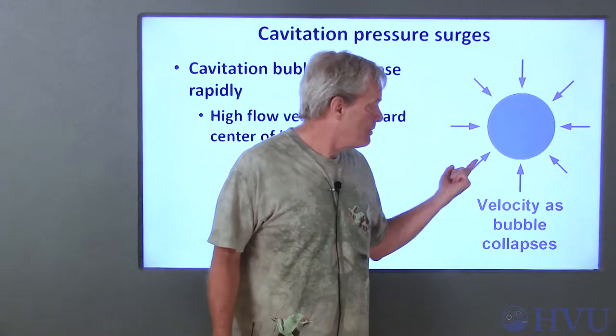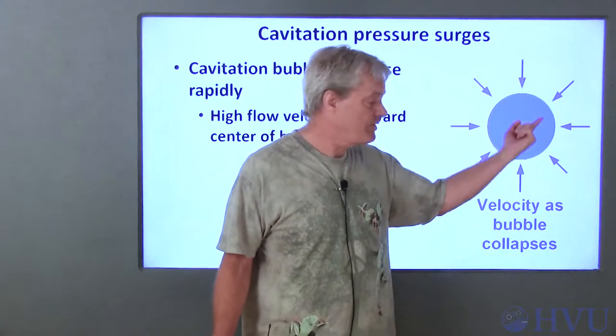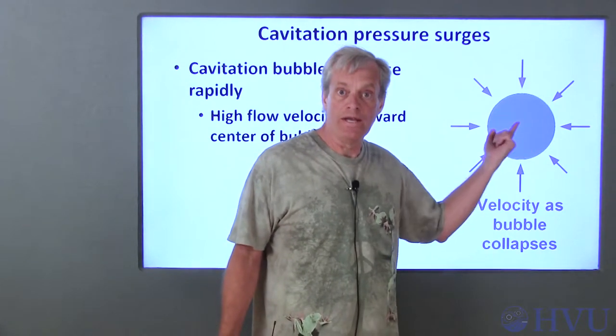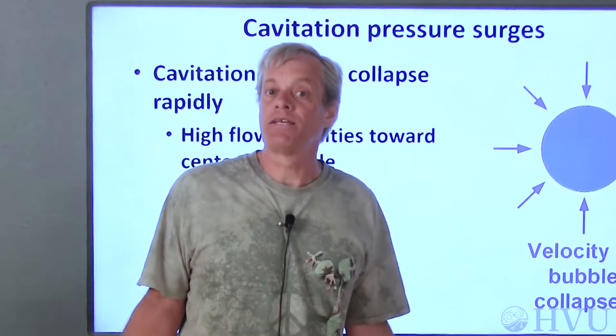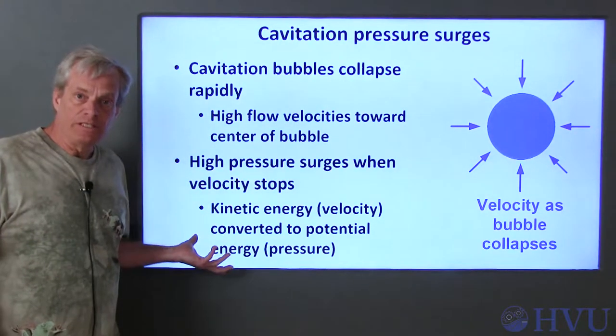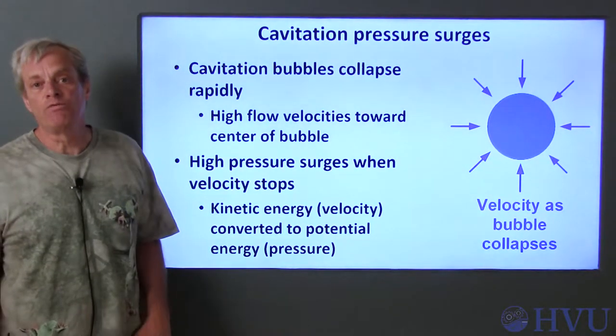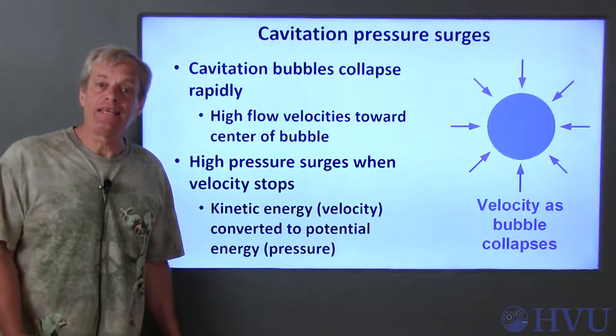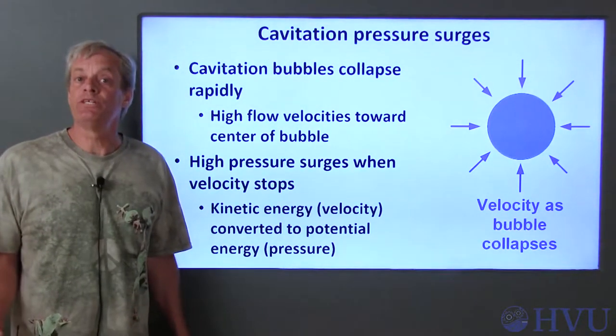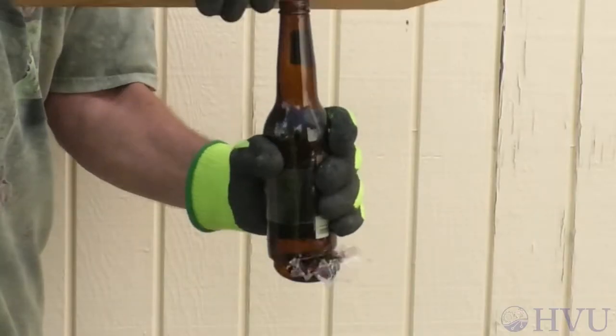As this bubble collapses, the fluid around the bubble is rushing in to fill this void. This means that the fluid replacing the bubble has a high velocity and a lot of kinetic energy. Once the bubble collapses completely, the fluid rushing in to fill the void has to stop suddenly, so the kinetic energy in the fluid is converted to potential energy in the form of very high pressures.